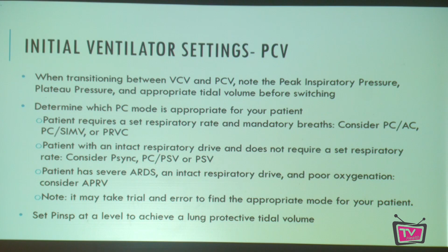First one we'll talk about is pressure control assist control. This is where we set an inspiratory pressure for mandatory breaths. And if the patient breathes over the set respiratory rate, so they're triggering breaths on their own, they're still going to receive that same set inspiratory pressure. On the side there is a graphic from Hamilton for their pressure control assist control ventilation. It shows your mandatory breaths and your delta pressure, and then that the patient can still trigger. I think number 5 is showing that triggering with that dip in pressure, and the resulting pressure control breath, which is at the same level as the inspiratory pressure we set for the mandatory breaths.